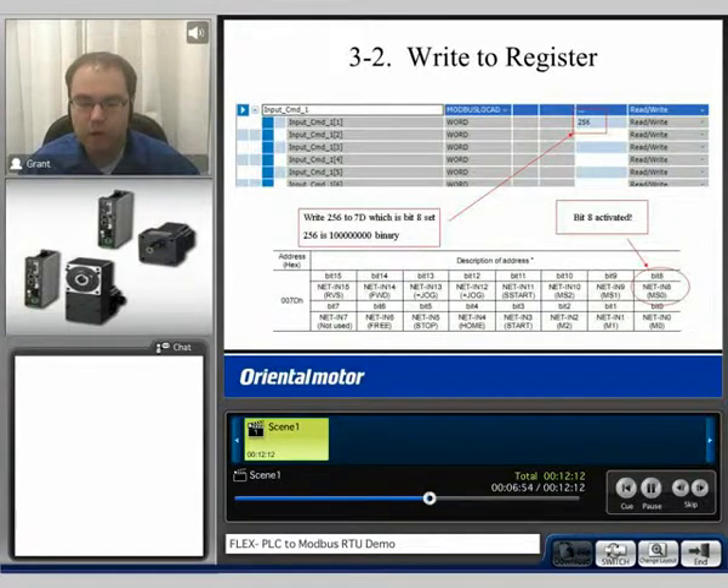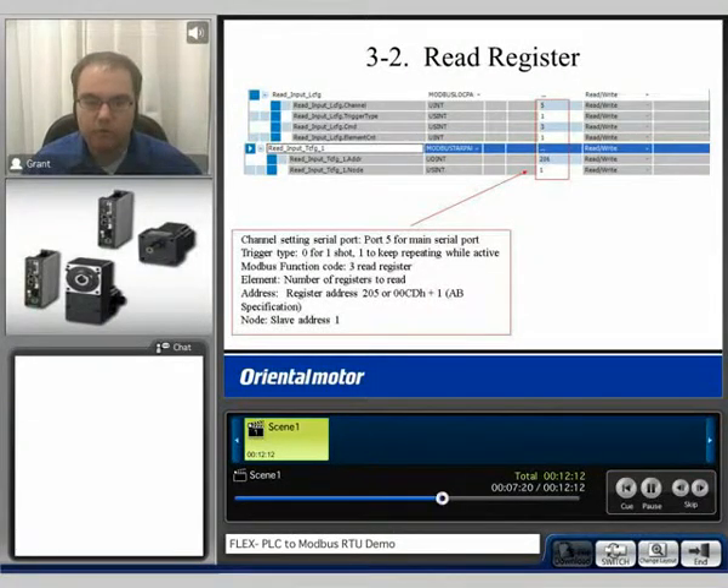Then we have to send the data of what we want to that register. For 7D, if we activate MS0 or bit 8, it will simply run the zero profile. Therefore, we can send 256, which is equivalent to 100000000 binary, and this will activate bit 8. When we read the register, it's the same steps repeated, except this time we selected 1 because we wanted to keep repeating while it was activated. The Modbus function code in this case was 3, which is read a register. We select 1 for the amount of registers to read. We wanted to read the position feedback, which is from the resolver — this is register address 205. Again, we have to add 1, so we actually enter 206 as the data. The slave address again is 1.